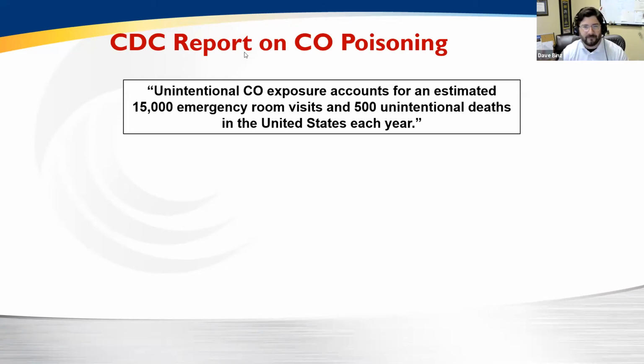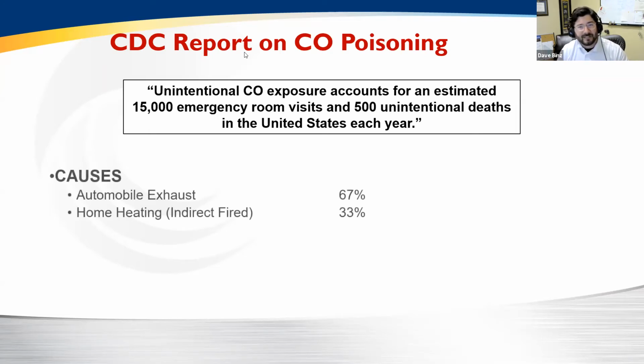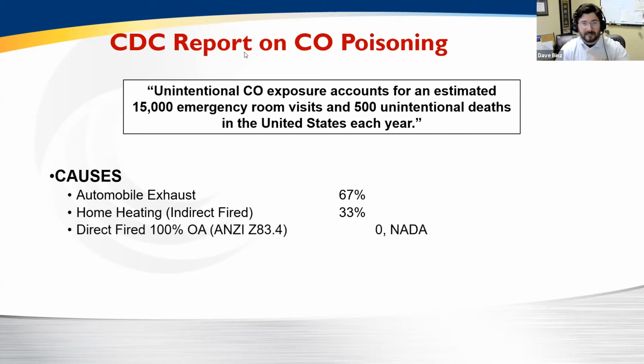What they found was that every year, about 15,000 emergency room visits are caused by carbon monoxide poisoning. And in those cases, about two-thirds are caused by automobile exhaust, and one-third are actually caused by indirect fired home heating systems. And inside that study, there have been zero exposures caused by a direct fired 100% outside air system.